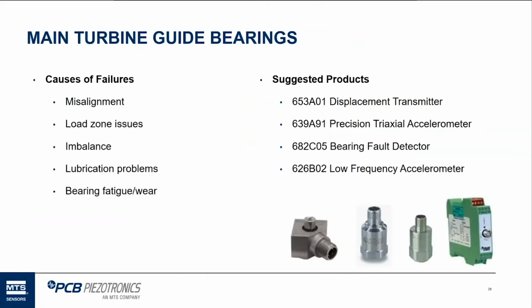Main turbine guide bearings typically have failures because of misalignment, imbalance, kind of the standard things. Could be load zone issues, and that could be related to improper flow to it, which would cause the turbine guide bearings to vibrate excessively. Of course, lubrication is always a problem on any kind of bearing, along with fatigue and wear of the bearing itself. So this is just a small sampling of the types of sensors we could provide for a main turbine guide bearing.